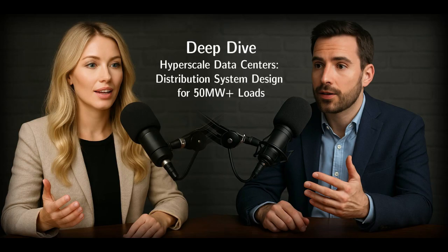Sure. For 15 megawatts, assuming a decent power factor like 0.95, your current is around 731 ampere. That's manageable with something like a 336 kcmil aluminum conductor. Voltage drop over, say, 5 miles might be acceptable, maybe 2.8%. Standard distribution protection gear is often okay. Cost-wise, you might be looking at around $800,000 per circuit mile for the line itself, plus maybe another $300,000 for the protection and control equipment at the substation end. So total, maybe $1.1 to $1.5 million per circuit.